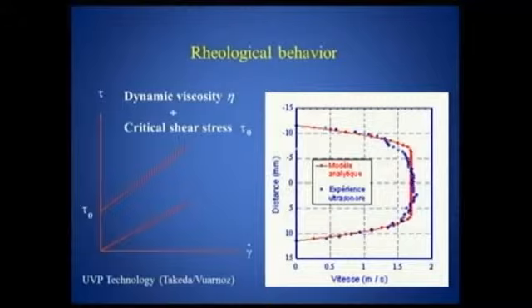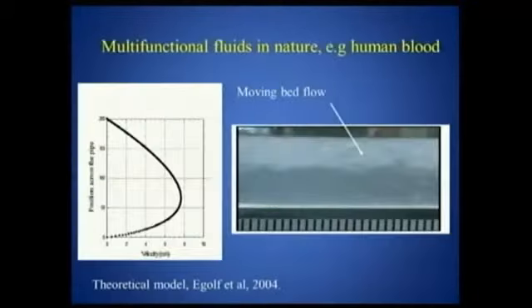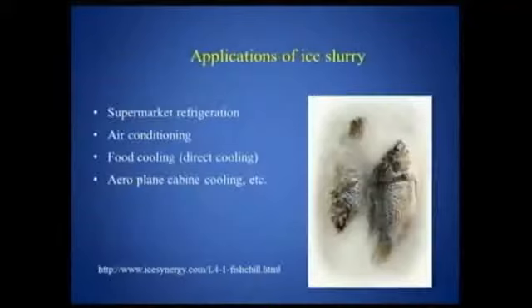on the right side. When the ice concentration goes towards 0, you get here the Poiseuille flow profile of a parabolic velocity profile. You see here also in the flow, when it's flowing, that we have this stratification. By this you have more ice at the top. There it's more viscous, so the velocities will be higher at the bottom, which you see on the left. That was modeled by one of my students in earlier time.